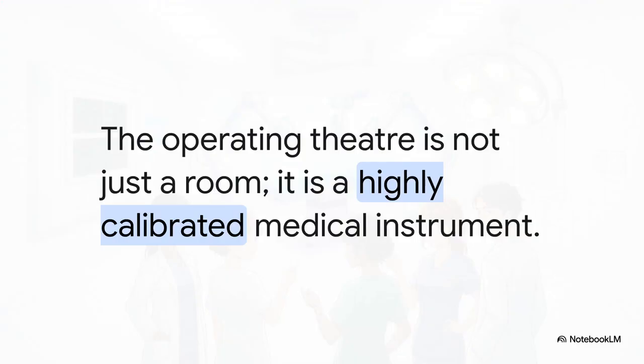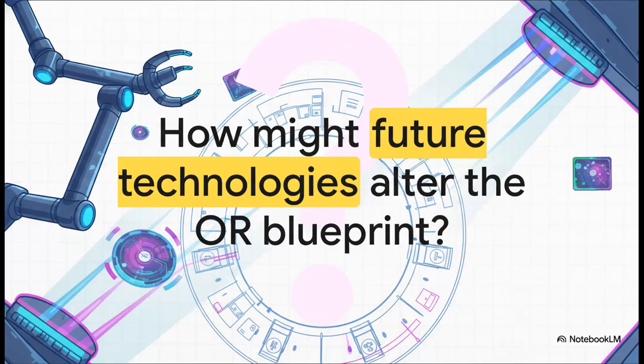So here is the ultimate takeaway we really want you to remember from this explainer. The operating theater isn't just a room where a procedure happens. The room itself is a highly calibrated medical instrument. From the precise 55% humidity levels preventing anesthetic explosions, to the outward-pushing airflow keeping bacteria at bay, all the way to the conductive casters grounding electricity, the physical environment is just as vital to a successful surgery as the surgeon's scalpel.